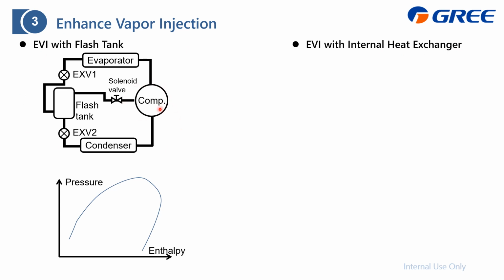We have the compressor, condenser, 2 metering devices for the metering, and also the evaporator. And also we have the flash tank and control the injection always with a solenoid valve. And here is how the refrigerant flows. Same, from the compressor is the high pressure and temperature vapor. Then we send this refrigerant into the condenser to release heat. Then it goes to here to become liquid. And then we send this liquid to the first metering device like the EXV.